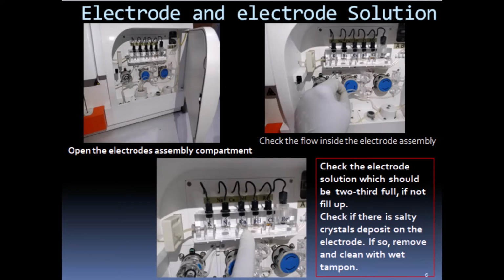To maintain the electrode, the assembly compartment is opened and the flow inside the electrode assembly is checked. Also, the electrode solution, which should be 2/3 full, is checked. If not, it is filled up. There is need to also check if there is salty crystal deposit on the electrode. If so, this is removed and cleaned with a wet tampon.